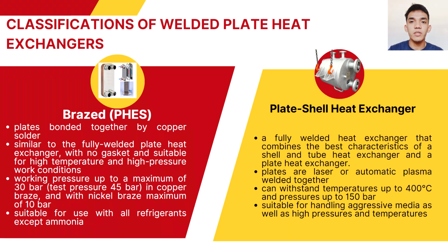Welded plate and shell heat exchangers are ideal for condensation and steam heating applications. The heat exchanger's fully welded plate pack makes them suitable for handling aggressive media as well as high temperatures and pressures. Furthermore, they are much lighter in weight and take up less space than shell and tube heat exchangers, making them an excellent replacement option. So, that's all for the classifications of welded plate heat exchanger.